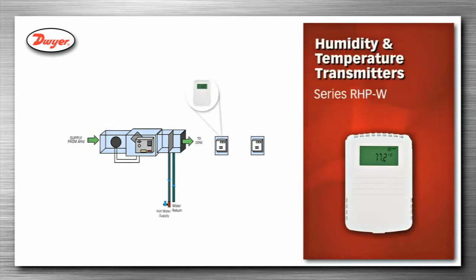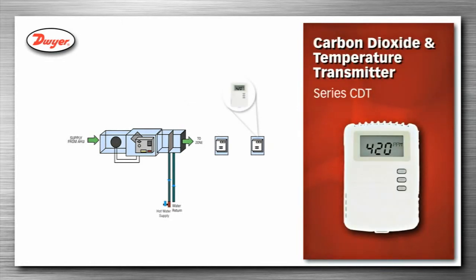Humidity and temperature transmitters, series RHP-W, are wall-mounted in the zone and used to monitor the zone air conditions and determine demand. Series CDT, carbon dioxide and temperature transmitter, are wall-mounted in the zone and used to monitor the concentration of carbon dioxide in the zone to determine the occupancy of the zone. The amount of airflow to the zone is then varied based on the occupancy.